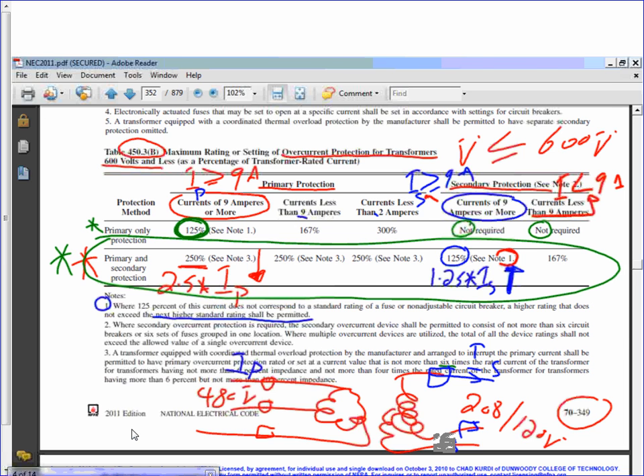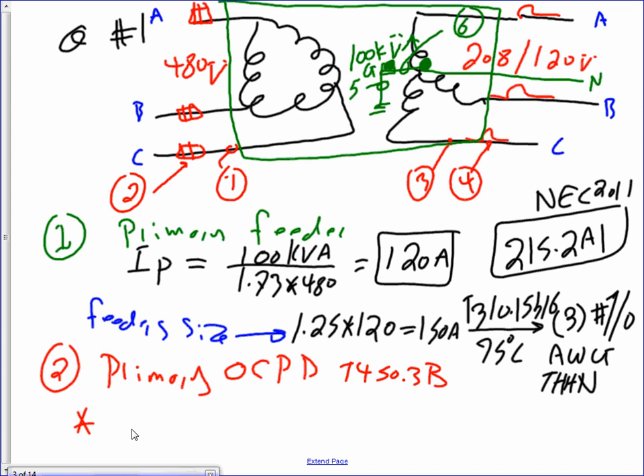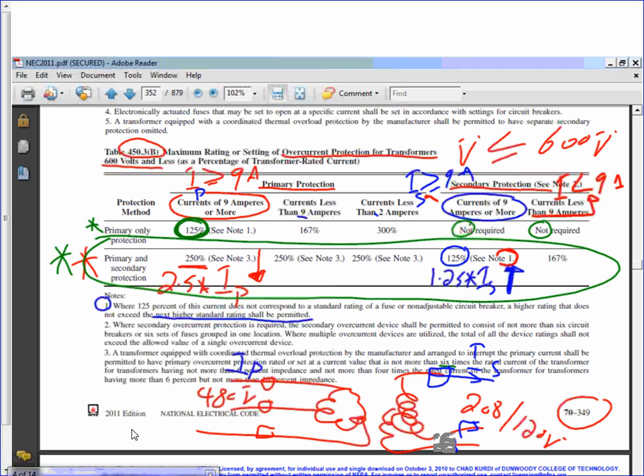Can you guys see that? Look at this. It's not primary. Here's a circuit breaker on the primary and the secondary. So we're going to go where? Then we are under the second row, which is the default. They're telling you guys for the primary current, you multiply 250. For the secondary current, if you're sizing the secondary, what do you multiply? 125. Can I have thumbs up, Chad? We fully understand how to use this table.